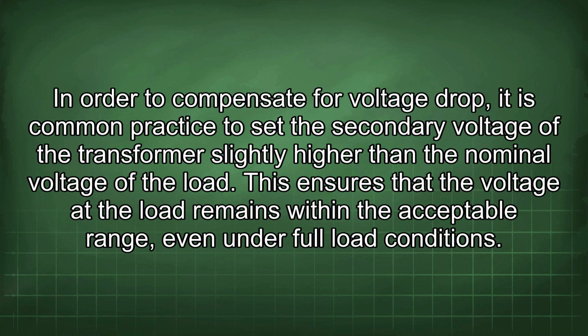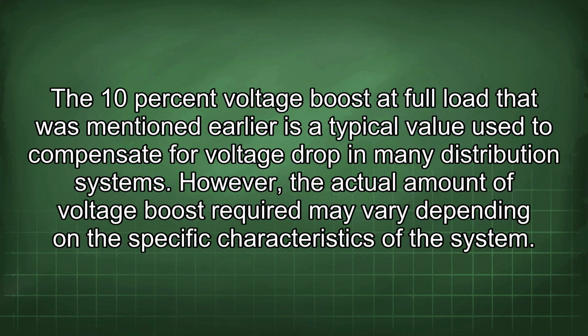In order to compensate for voltage drop, it is common practice to set the secondary voltage of the transformer slightly higher than the nominal voltage of the load. This ensures that the voltage at the load remains within the acceptable range, even under full load conditions. The 10% voltage boost at full load that was mentioned earlier is a typical value used to compensate for voltage drop in many distribution systems. However, the actual amount of voltage boost required may vary depending on the specific characteristics of the system.